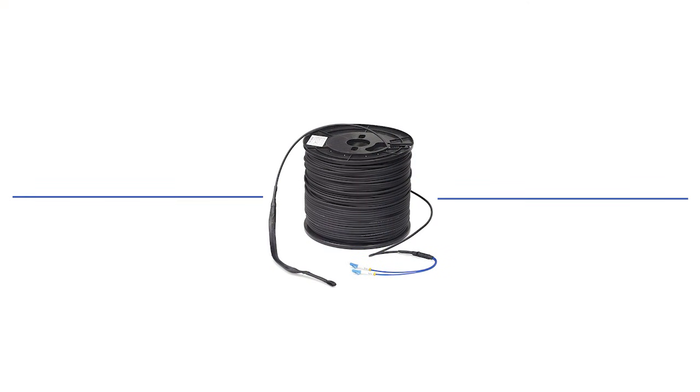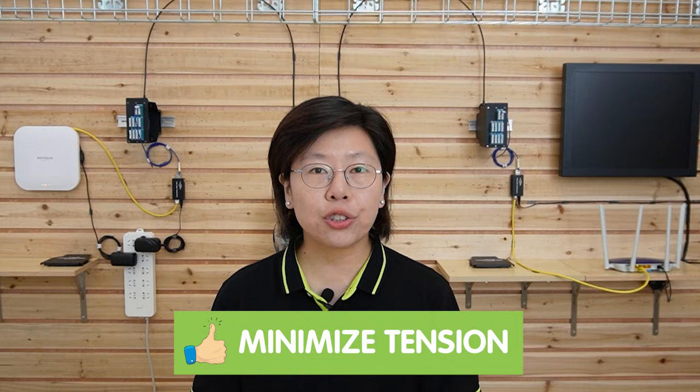Pulling and installing fiber optic cable requires precision and care to avoid damage and signal loss. For extremely long distances, it is often more efficient to pull the cable from the middle toward both ends — this minimizes tension on the cables and reduces the risk of damage. During installation, it is advisable to have a two-person team: one person pulls the cable while the other carefully guides and releases it. After installation, it is essential to secure the cable properly, especially in racks or conduits.